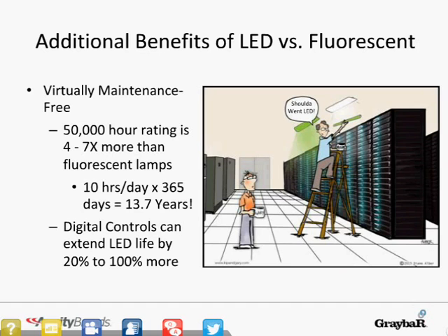To further illustrate this point, if the fixture is on for 10 hours a day, 365 days a year, then the typical LED will last 13.7 years. That's a long time. Now, when you add in digital controls on top of that, useful life can be extended an additional 20 to 100% or more. Savings like these have never been seen before in the lighting business. It's really, really incredible.